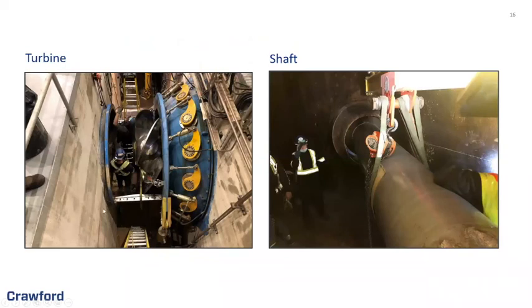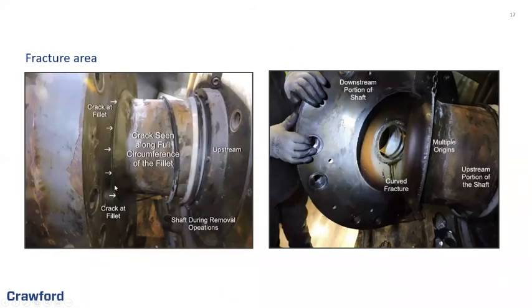Here's a better picture of the turbine itself and the shaft over here. So we hired the mechanical engineer to determine the cause, which was a design failure within the shaft. This unit is about 10 years old, if I'm not mistaken. The next photos here will show there was a fracture, a crack right here at this point, and it was just a poor design.